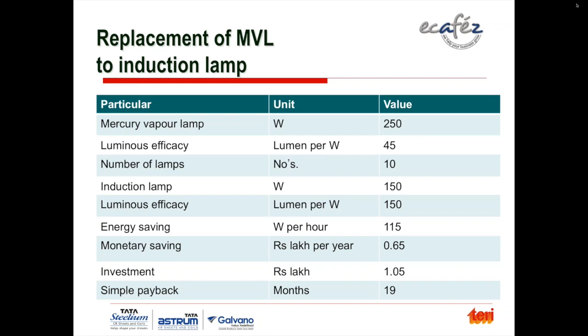Here again, I would like to mention on lighting that LED has of course now come into the picture. LED lamps are typically very efficient, but they have a life of 50,000 working hours, compared to 80,000 or up to 1 lakh hours. So induction lamps have a higher life than LEDs also. LEDs are good for indoor lighting or lighting in a clean environment, but outdoors or in a very polluting, dusty environment within the plant, dust may deposit on the fins of the LED lamp, which can raise the temperature of the LEDs, because the light emitting diodes need to operate at a certain temperature for higher efficiency.